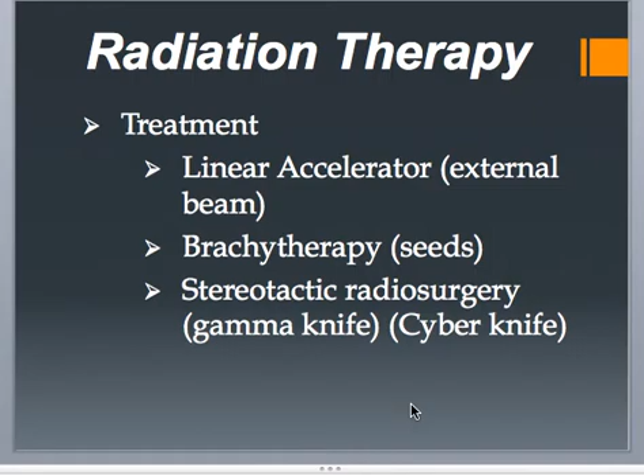So going back to this one, these are the couple different machines. So you've got the Cobalt 60 first, and then the 2 linear accelerators. So the Cobalt 60 system is not necessarily the Gamma Knife. Most of the Cobalt 60 systems have been replaced with linear accelerators. Cobalts just can't deliver the high power of radiation that a linear accelerator can. Also, one of the biggest downfalls is the radiation produced from a Cobalt 60 system cannot be turned off. So the radioactive source is always on. I repeat, for the Cobalt systems, the radiation source cannot be turned off. So the radiation is always on with those. So that's a downfall. They actually have like a big lead shutter that encloses the machine so it's not emitting radiation out, but it is a downfall for that machine to not be able to be turned off.